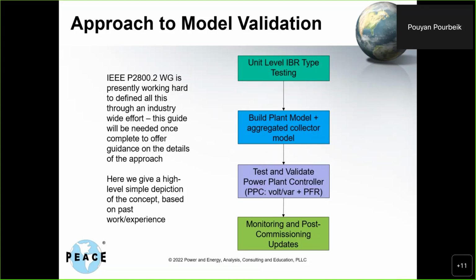The idea is you do unit-level individual IBR testing - individual wind turbine, individual PV inverter, individual battery inverter, whatever - type testing, say in a factory, and you verify the model of that individual unit. Once you're happy, you move to the next box, where you build that plant aggregate model we just discussed, both in power flow and dynamics.